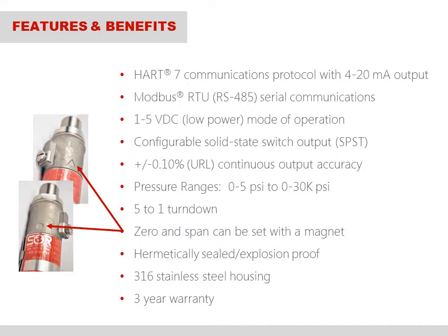It goes without saying, but is worth noting, the 815PT is a best-in-class stick transmitter. All model number configurations provide as standard the following outputs and communication capability. The popular 4 to 20 milliamp and the 1 to 5 volt DC low power mode of operation outputs, a configurable solid state switch output. This is a single pole, single throw, normally open relay that is rated for 30 volts DC and 120 milliamps. HART 7 communications protocol and Modbus RTU serial communications.